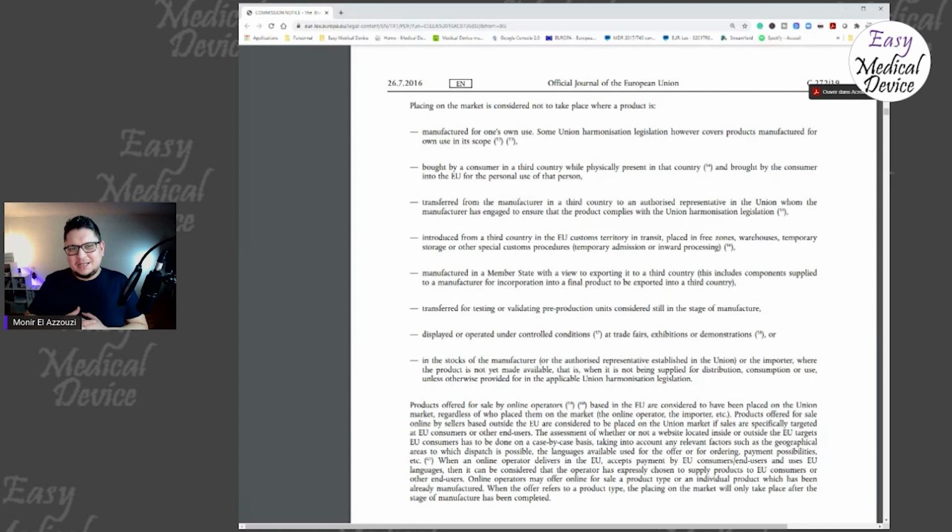So you have to be aware of the law, and you cannot say, oh, I didn't know. You know that as soon as there is a significant change, the product is no longer CE marked under MDD, and then you have to get an EU MDR certificate. So you need an alert button: as soon as we see that, we have to stop distribution, because you are also liable per the economic operators' requirements.